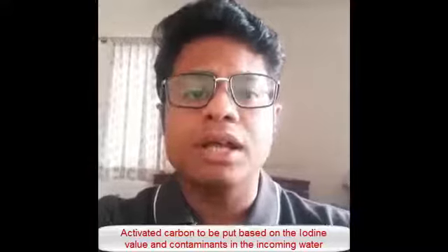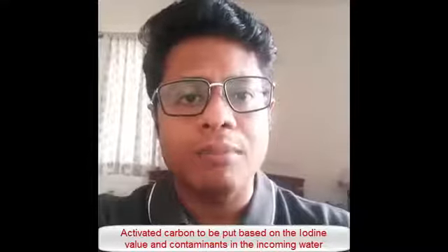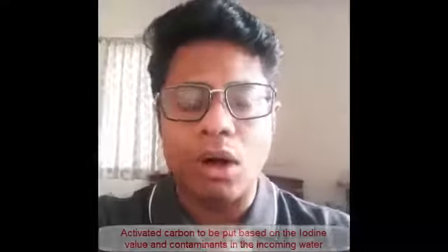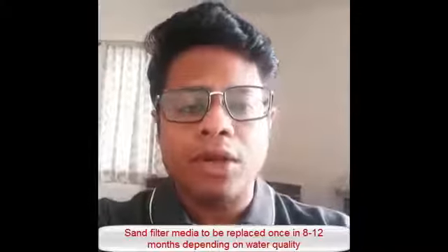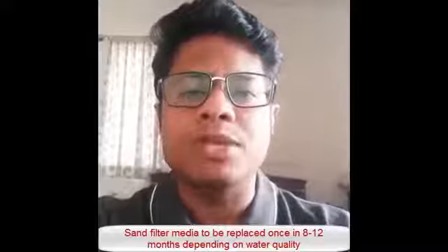When you replace the media for a carbon filter, you should know that the carbon used is specific to your water quality. For example, carbon is graded based on iodine value. Some carbon is impregnated with special materials to remove special contaminants from your water. For the sand filter also, depending on your water quality, you might have to replace it once in 8 months to a year.